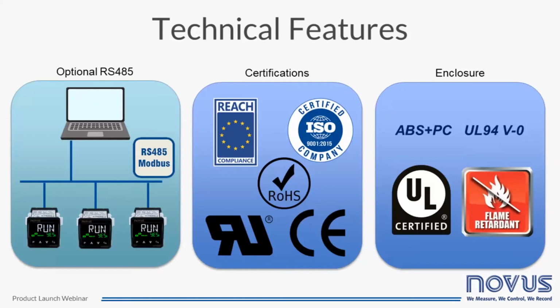N1050 has a model with optional RS-485 interface, which uses Modbus RTU slave protocol, enabling its use in a network. The controller has CE mark and is UL listed. Beyond that, Novus is an ISO 9001 certified company, and its RoHS and REACH compliant approvals are demanded in some global markets. N1050 has an enclosure injected with UL 94 V-0 blend of polycarbonate and ABS, which makes it flame retardant. It is one of the few in the world market that has it.